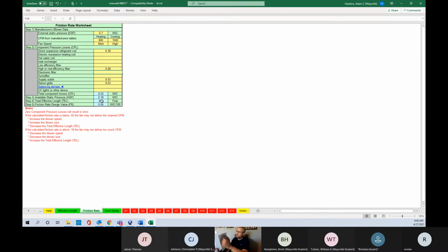All right, so I'm up to the top right here. I'm going to go to 0.1, and I'm going to look at my round duct diameter to move 1,000 CFM, and then my equivalent rectangular. So 0.1 at 1,000 is about 14-inch duct. And it takes what size rectangular? James, what's it take? You got yours? 10 by 16, or 8 by about 20 or 22. All right. Now slide your duct slide to 0.04 at 1,000.